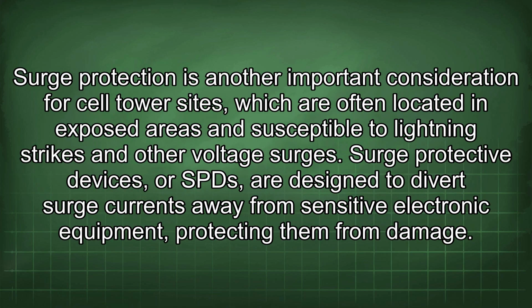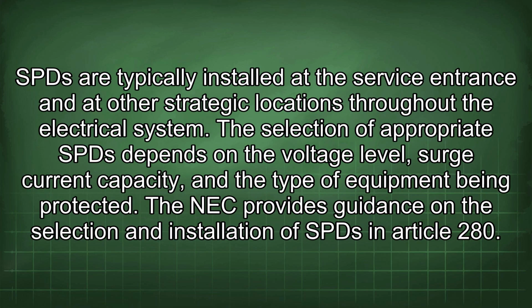Surge protection is another important consideration for cell tower sites, which are often located in exposed areas and susceptible to lightning strikes and other voltage surges. Surge protective devices, or SPDs, are designed to divert surge currents away from sensitive electronic equipment, protecting them from damage. SPDs are typically installed at the service entrance and at other strategic locations throughout the electrical system. The selection of appropriate SPDs depends on the voltage level, surge current capacity, and the type of equipment being protected.